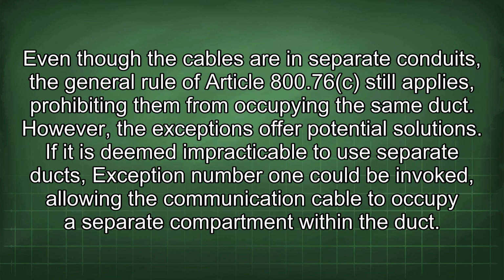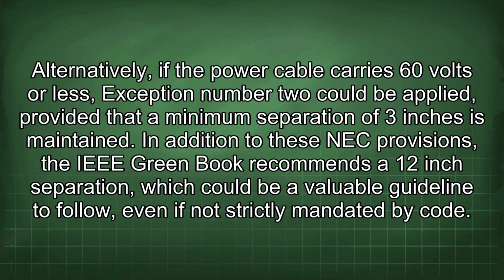Even though the cables are in separate conduits, the general rule of Article 800.76 still applies, prohibiting them from occupying the same duct. However, the exceptions offer potential solutions. If it is deemed impracticable to use separate ducts, exception number 1 could be invoked, allowing the communication cable to occupy a separate compartment within the duct. Alternatively, if the power cable carries 60 volts or less, exception number 2 could be applied, provided that a minimum separation of 3 inches is maintained.